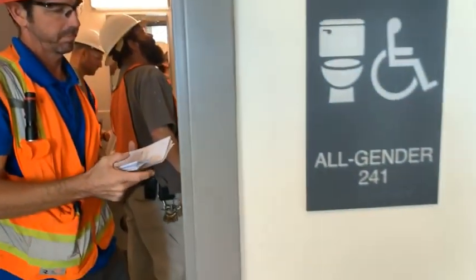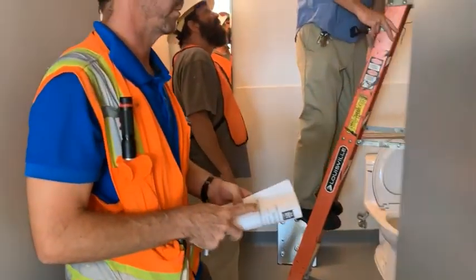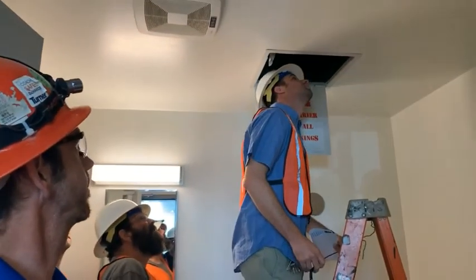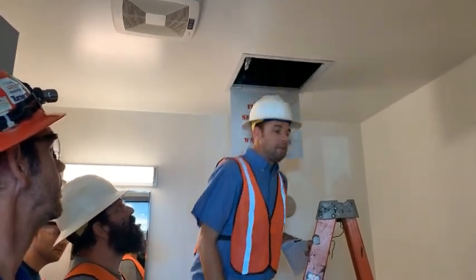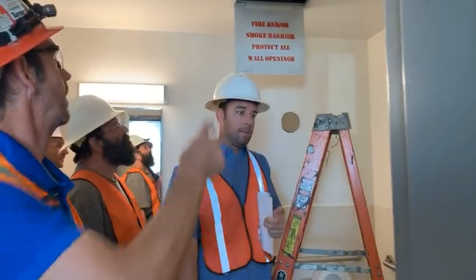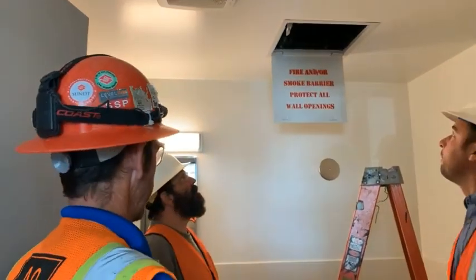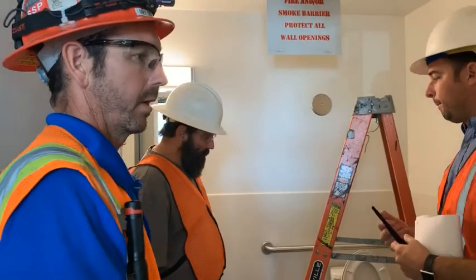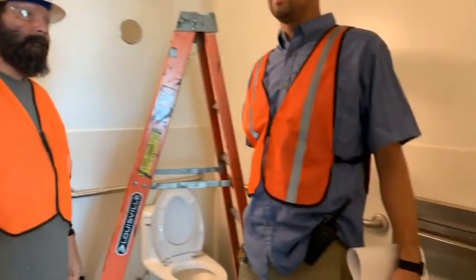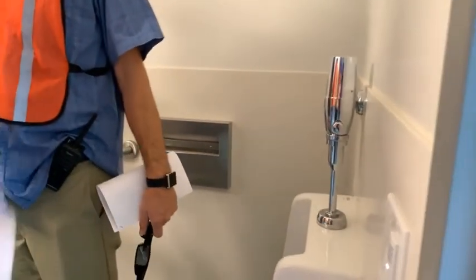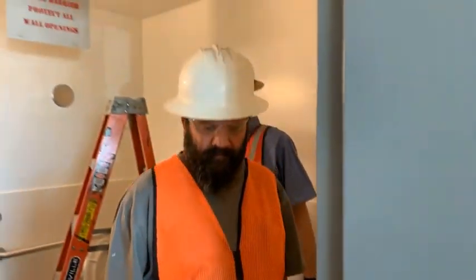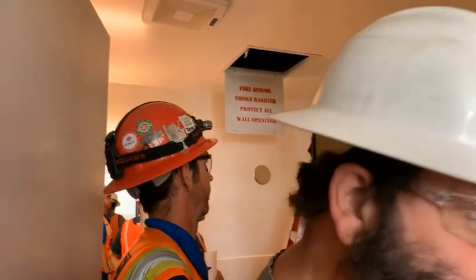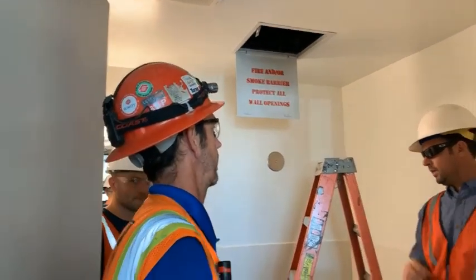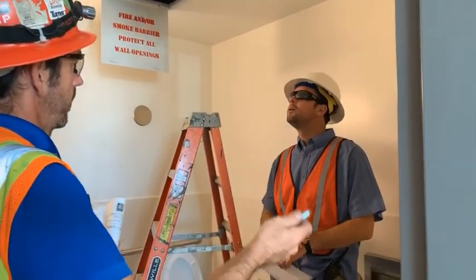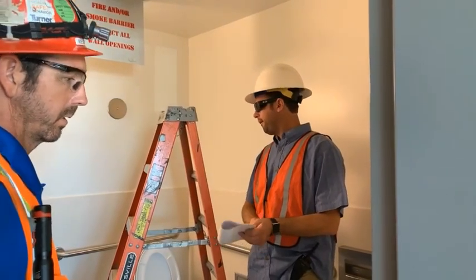So this is typical. This is a guest restroom. This will be typical 2 through 8. Again, the main shutoff valves are up here. You can isolate the toilet and the sink and the urinal individually if need be. You don't have to shut off the whole restroom to service one part of it, but you can. Sometimes it's just easier that way. It depends what the issue is.